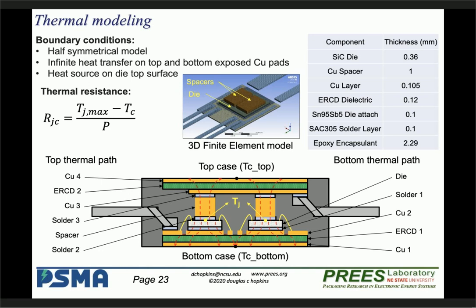Does the choice of spacer depend on whether the die is silicon, silicon carbide, or GaN? If so, how? So, from a mechanical reliability perspective, silicon carbide and gallium nitride may have different CTE or modulus, so yes, it can affect the result. It doesn't necessarily need to be a copper spacer - it can be another material or another thickness. It's not necessary to fix it at copper, because the device can have different material properties, yielding different rigidity in the power module.